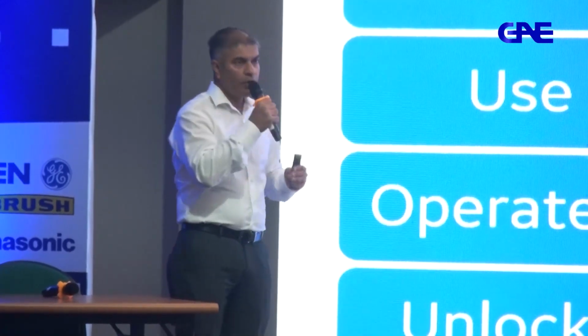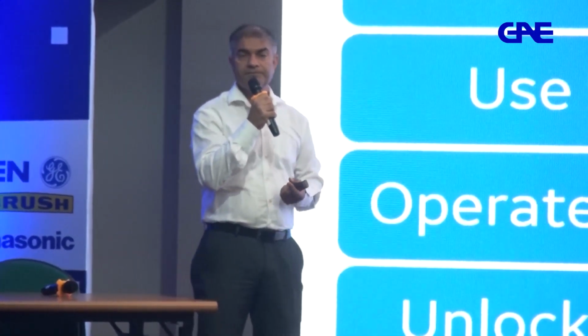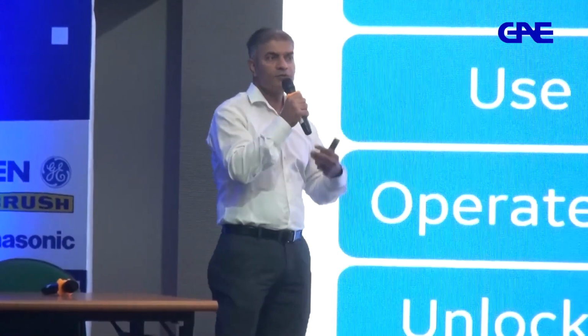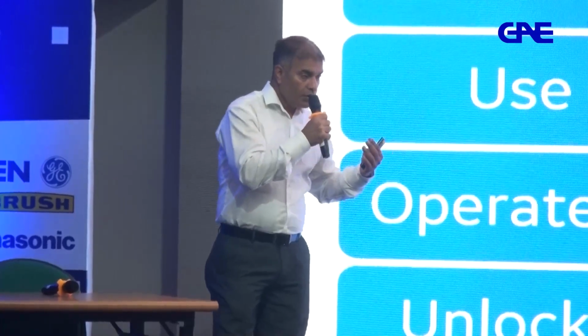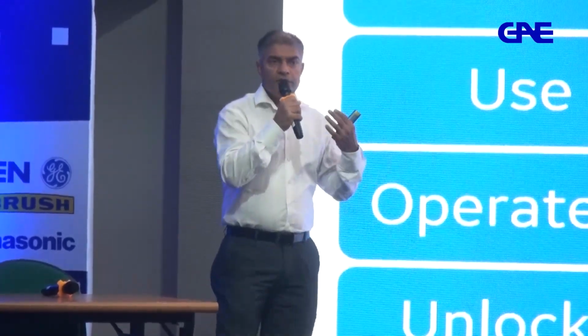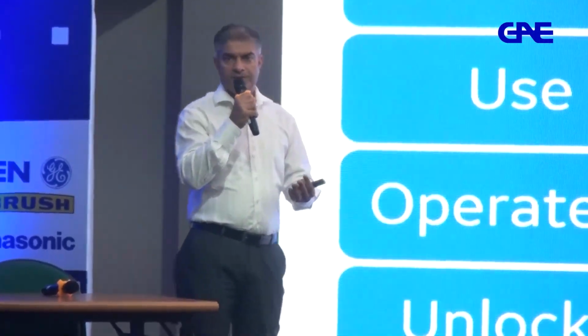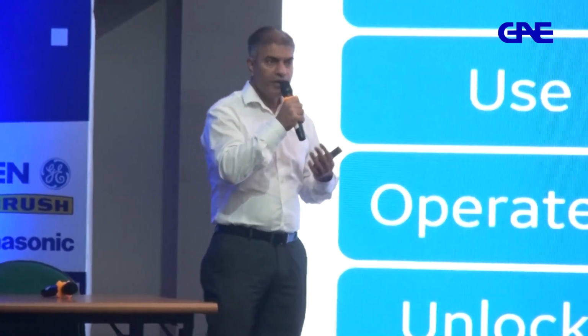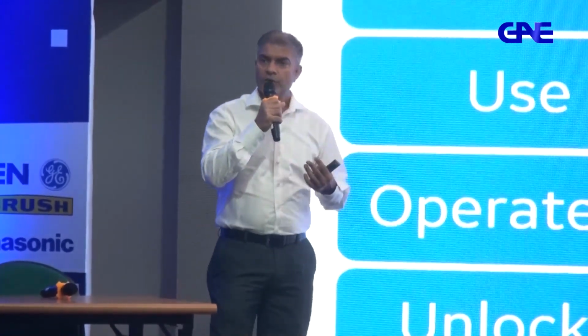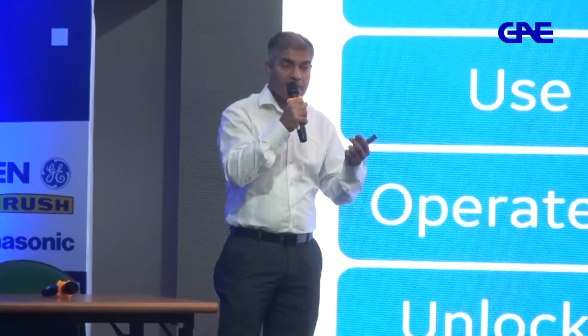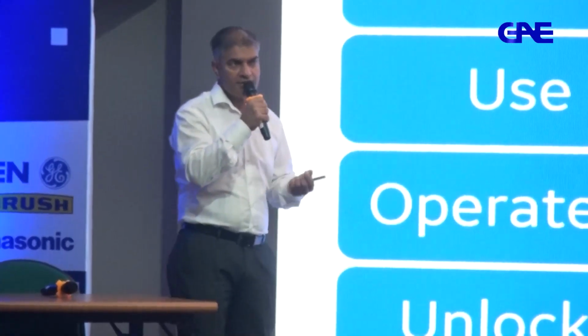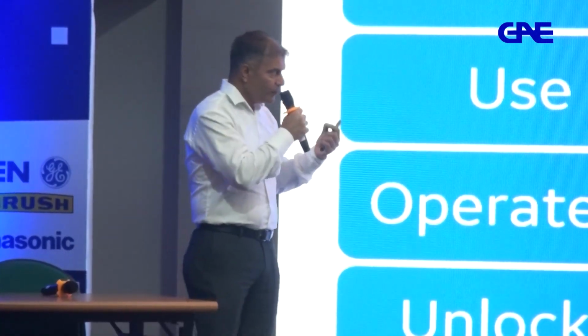Monitoring is better because now we are dealing with data, sampled value signals, GOOSE signals, etc. This data is very easy to monitor, and if you are able to monitor the data, there is less need for testing. The testing requirement in a digital substation is very limited.